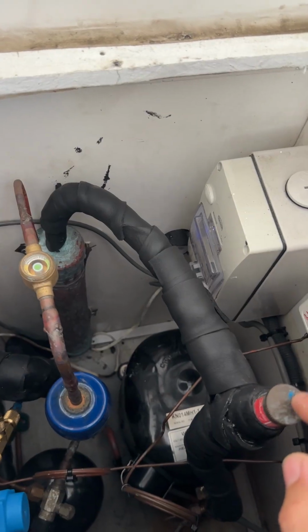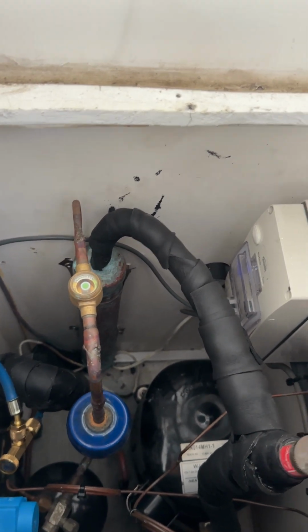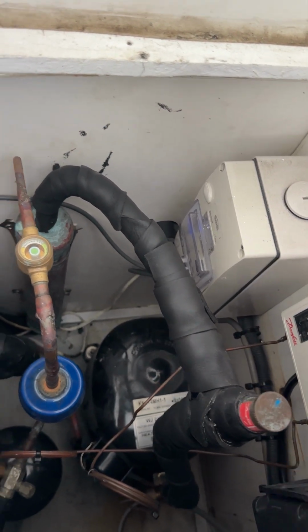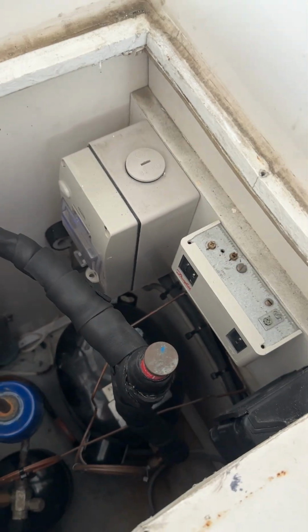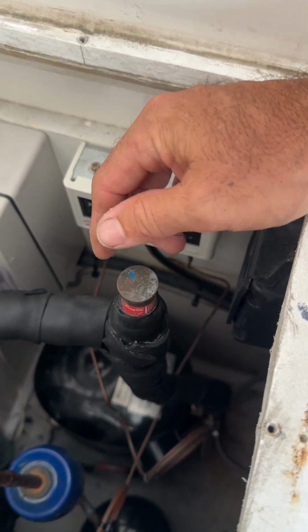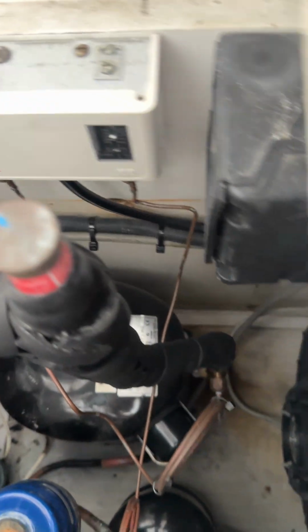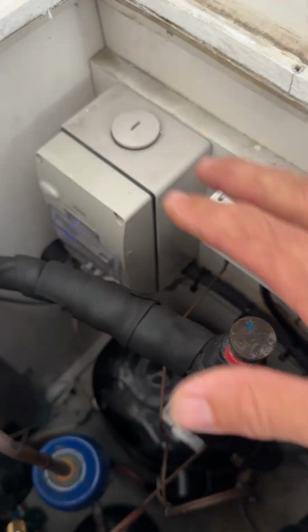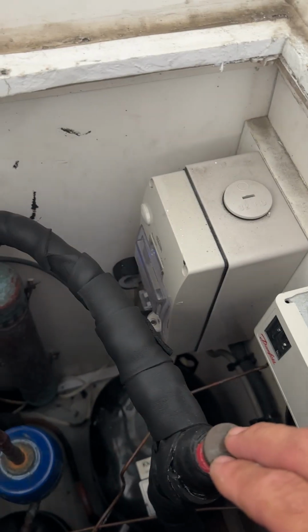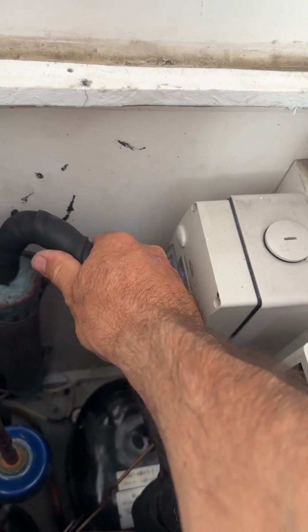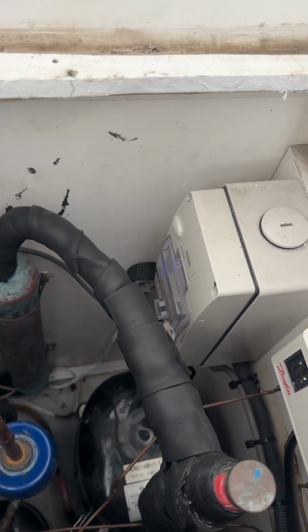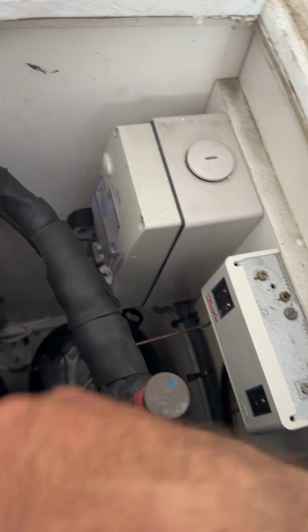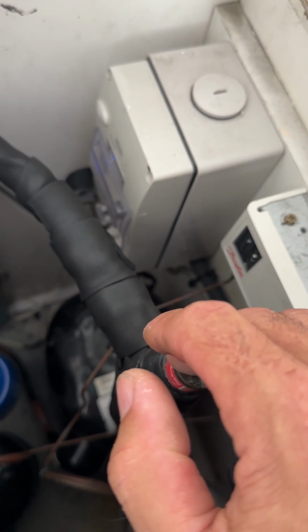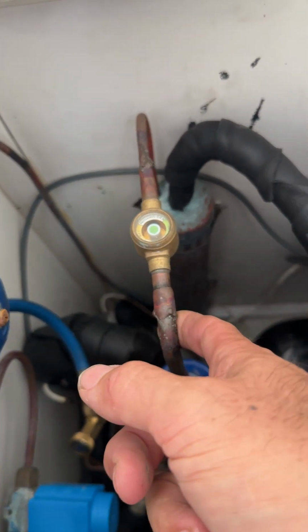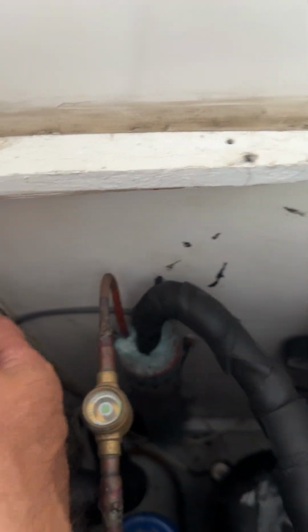So these liquid suction heat exchangers do have a good couple of features when you use them. Typically in a low temp system like this, aiming for about -18, -20 inside the box, what normally you'll see is the CPR or this return pipe working here from the compressor back just turn a solid block of ice, and then when it defrosts, you get all this water puddling there, and sweating on the pipe work. So that is a bit of a bonus. It means insulation doesn't have to be as critical. Not that it should be subpar, but normally these CPRs and all this pipe work coming back here just start freezing up because the return gas is so cold. Because you're taking the cold and exchanging it with this, you're also putting energy back into the system and you're cooling down the pipe work.